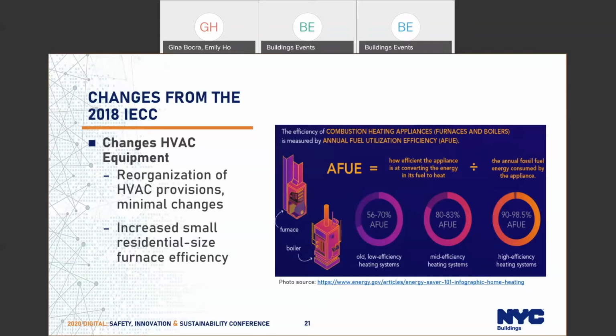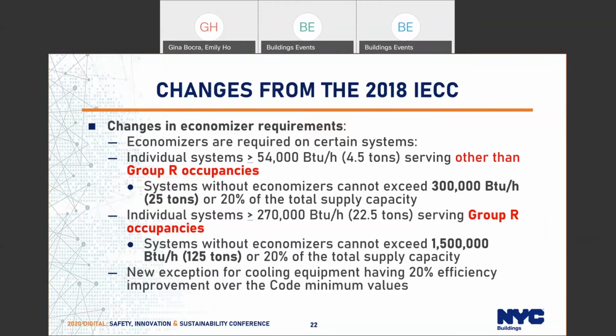So, definitely check out that resource on our webpage to see what's new, what new sections are, and how they correlate to the 2016. As far as efficiency increases, there weren't many. The biggest change was that for small residential size furnaces, there was a small increase in efficiency there. So, that may apply to smaller residential buildings. There was a change in the economizer requirements.